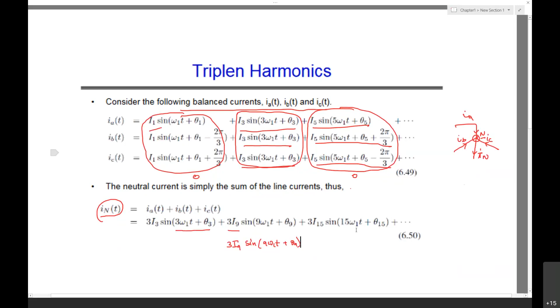What are the implications when we allow the triplen harmonics? Transformers with a neutral connection, grounded, experience overheating when serving single phase loads on the Y side of the transformer. In the distribution side, the transmission side is delta. Because of that, on the delta side the triplen harmonics will be circulating within the winding, whereas on the distribution side all the triplen harmonic currents are going to flow in the neutral. We have overheating when serving single phase loads on the Y side of the transformer.